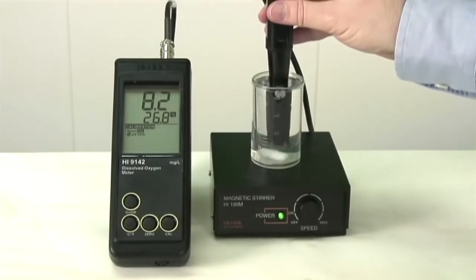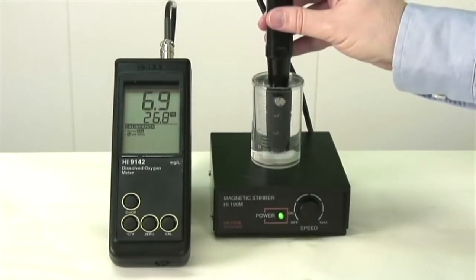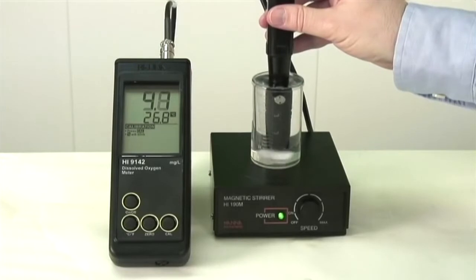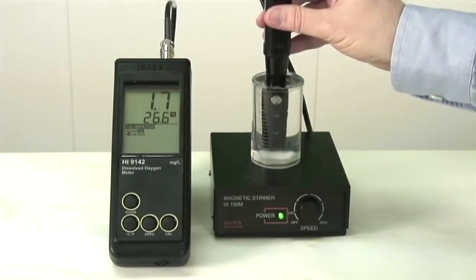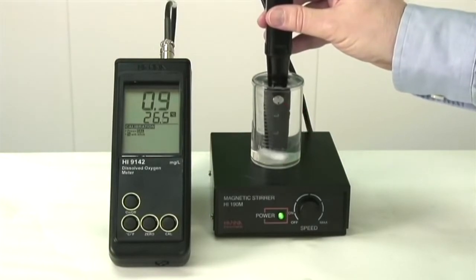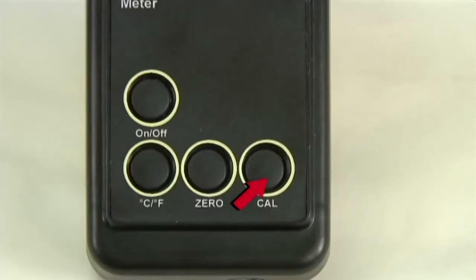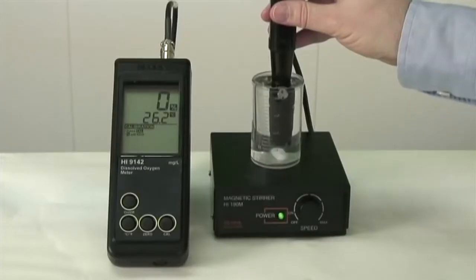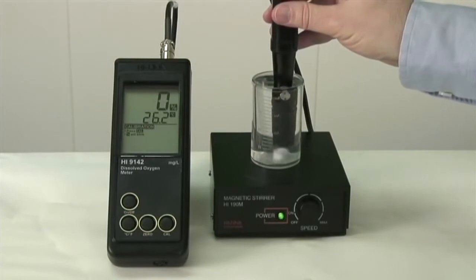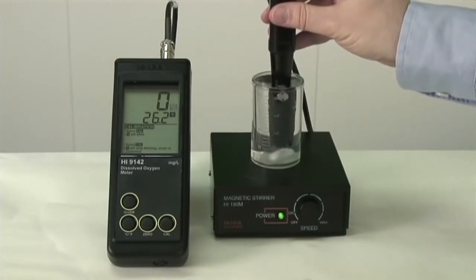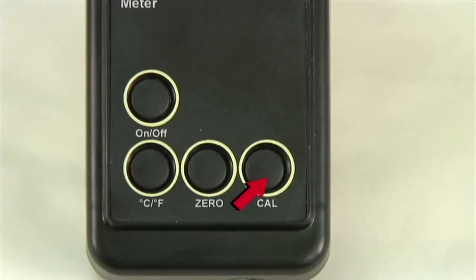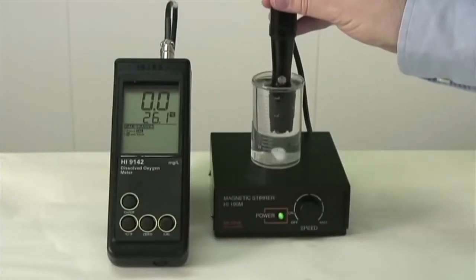Submerge the probe in the zero oxygen solution and stir gently for a couple of minutes. Since this is typically a field meter and we're not in the field, we'll be using a magnetic stir plate to stir our sample. Stirring your solution when calibrating and measuring is important to ensure accurate readings. Make sure the temperature sensor is submerged as well. This is critical. After stirring a couple of minutes, press and hold down the cal button and press the 0 button. The percent tag will blink until stabilization. When the Press Cal message appears, press Cal to confirm and exit the 0% calibration.